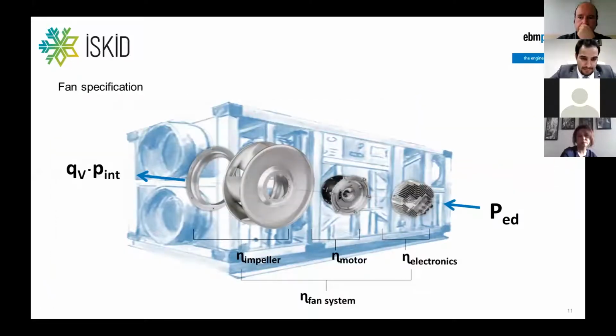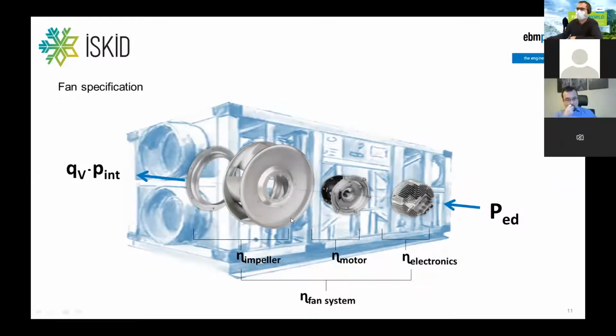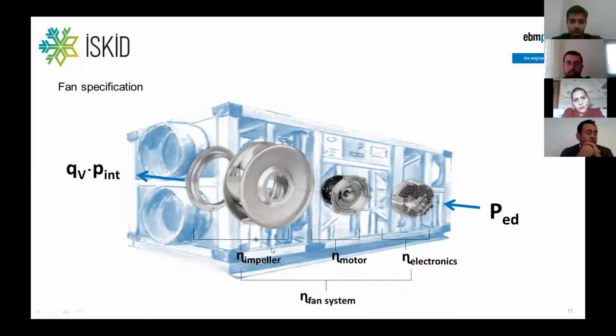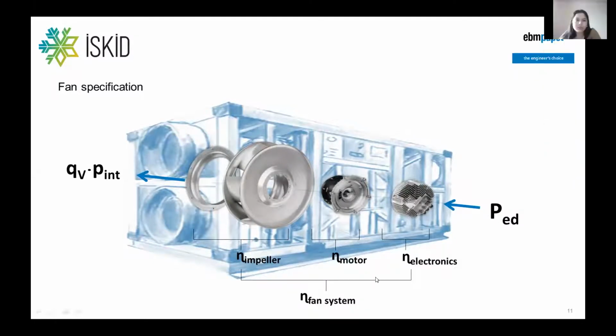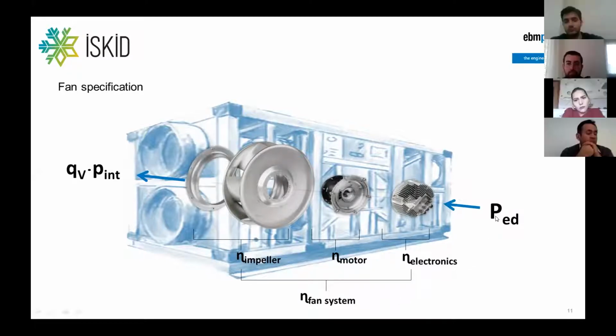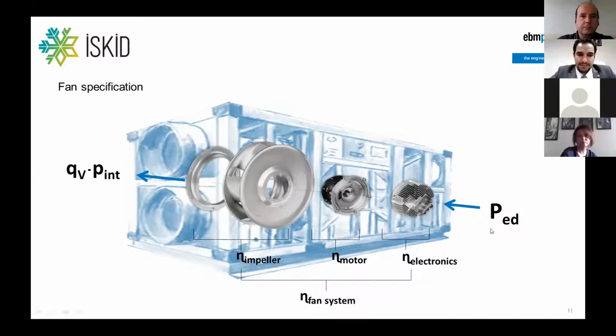So the fan is, let's say, the machine that consumes the most energy, besides a compressor, in an air handling unit device. The amount of air is always more or less fixed. What the fan manufacturer tries to create is an efficient fluidic flow machine, which is the impeller, an efficient motor, and an efficient drive. So this is the fan system efficiency. It's always the target to have the lowest power input to do a certain job.